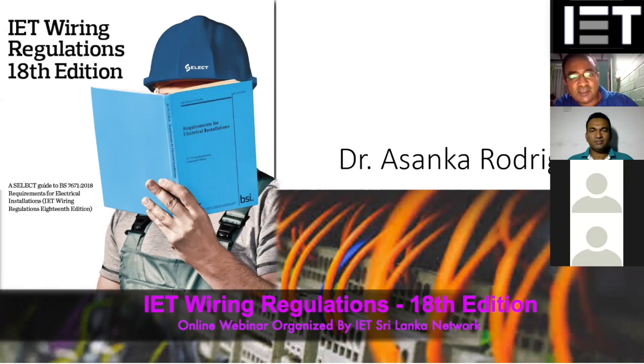And then the next question is, are existing installations to be modified with these new additions of the 18th edition? Yeah, whatever augmentation or modification is done should comply with this requirement. It very clearly says so. In the IET wiring regulations, there is a part on alteration or augmentation of the installation. It clearly says that the prevailing, current rules and regulations should apply to the alterations and extensions. But the existing installation can remain as it is. If you do any modification, then you have to comply with the new requirements.